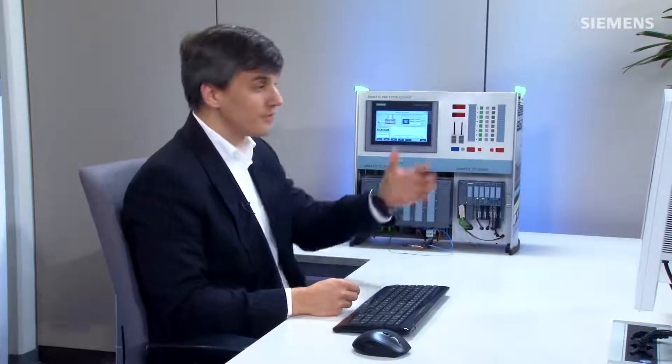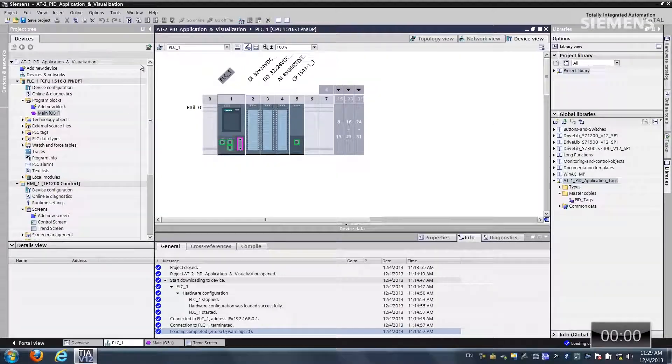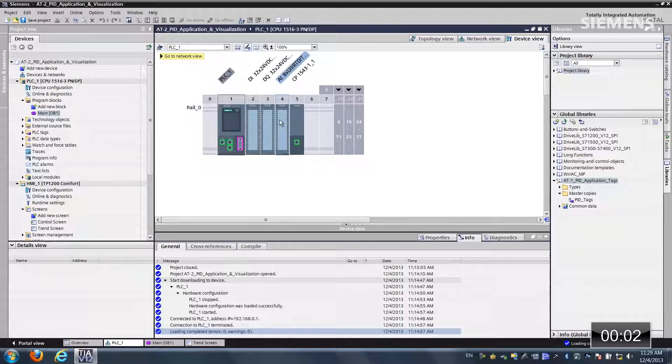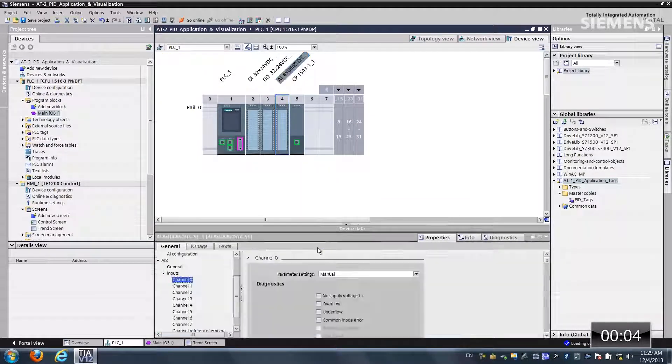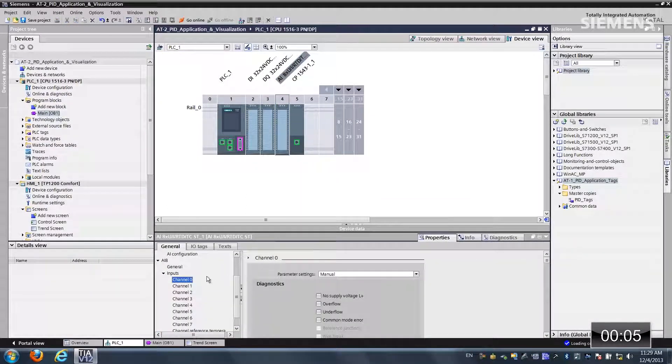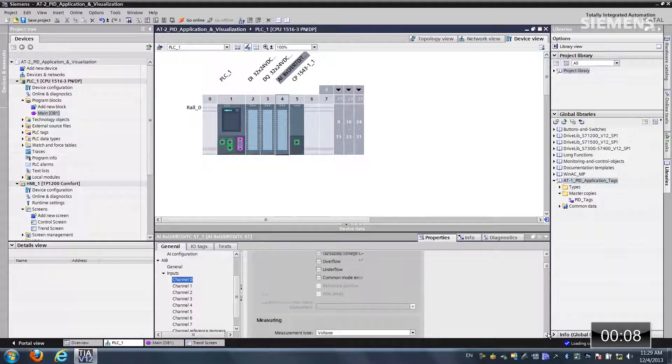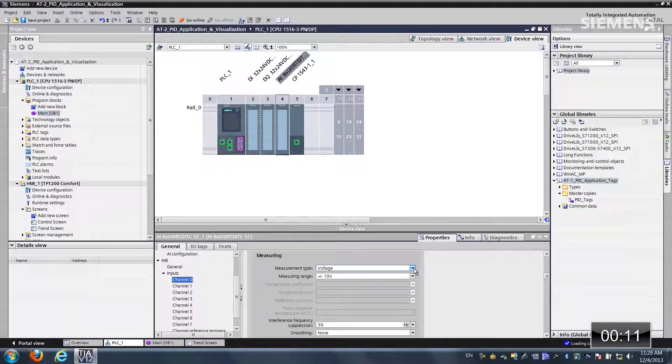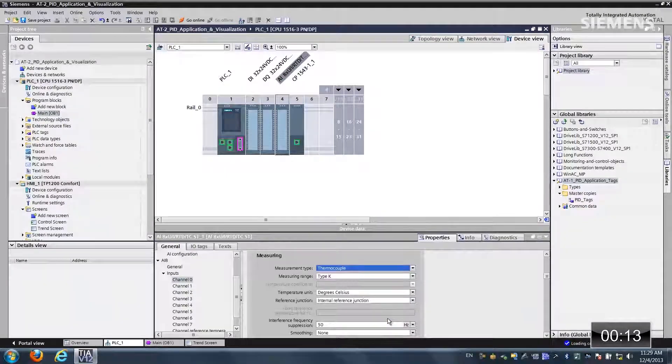The first step is here in the hardware configuration section. I want to give focus to our analog card, right-click and choose properties. Channel 0 is where the thermocouple is wired into, so I want to go down to the measurement section of this channel and change it from voltage to thermocouple.